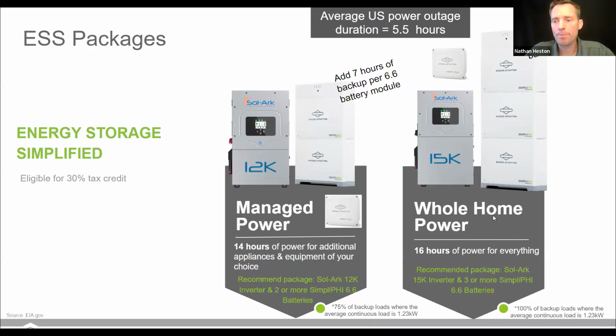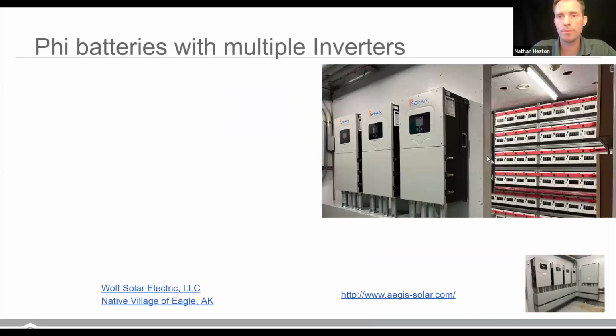Similarly, on the whole home backup, we were talking about how now everything is going to be backed up. So you're looking at 1.23 kilowatts of power coming out of these batteries continuously. And you should get about 16 hours of power from that 20 kilowatt hour stack. Of course, you can have multiple stacks, up to 16 of these stacks with a single inverter. And there's no harm in having a very large battery bank and a smaller inverter. You just can't really generate maybe the necessary power, but you'd have a long backup time that way. So you can always add batteries if you want additional time.